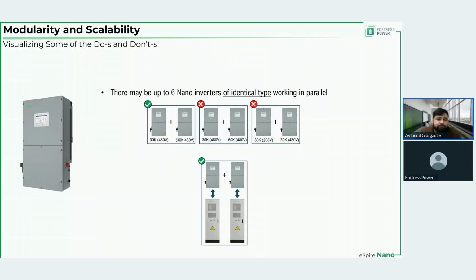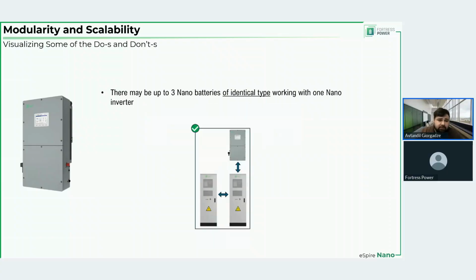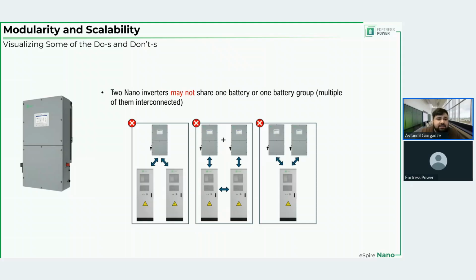As I was saying before, it is okay for each inverter to have its own battery. So there is no connection between the inverters and the batteries on the DC side. One battery connects to one inverter in this case, but one inverter does not have communication to the other battery. It only works with its own battery, but they are interconnected on the AC side. If you want to have multiple batteries per inverter, this is the way to do it, as you see right here. And these are the things that you cannot do.